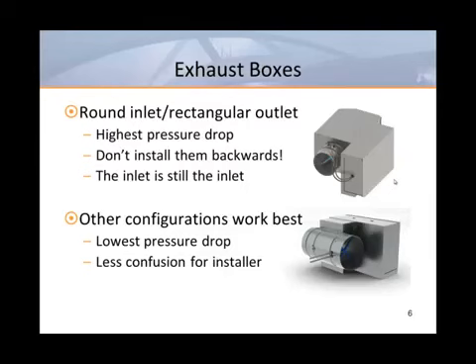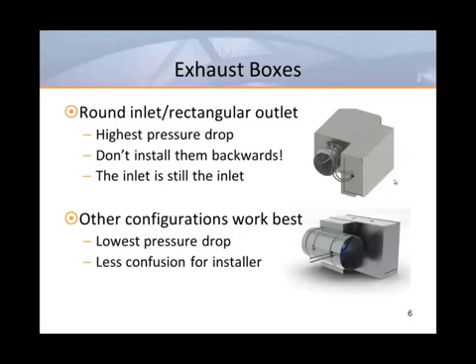All of these problems can be avoided by either selecting a purpose-built exhaust box or using a retrofit air valve with a round inlet and a round outlet. It should be noted that currently there is no industry standard for testing or rating exhaust box performance, but luckily ASHRAE Standard 130 and AHRI Standard 880 will soon be revised and expanded to cover exhaust boxes.